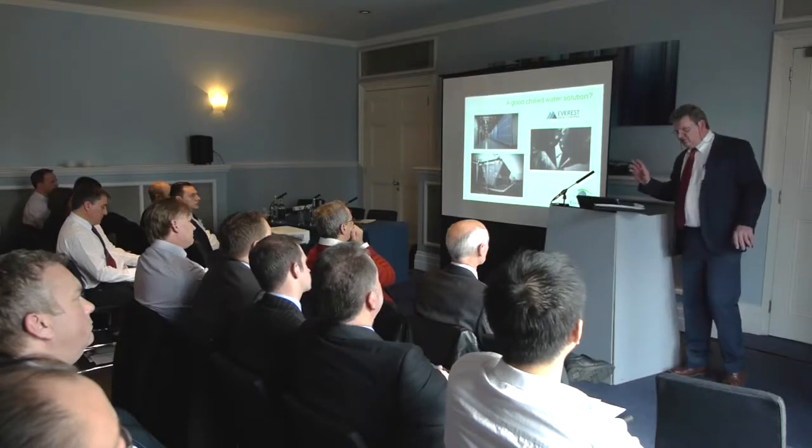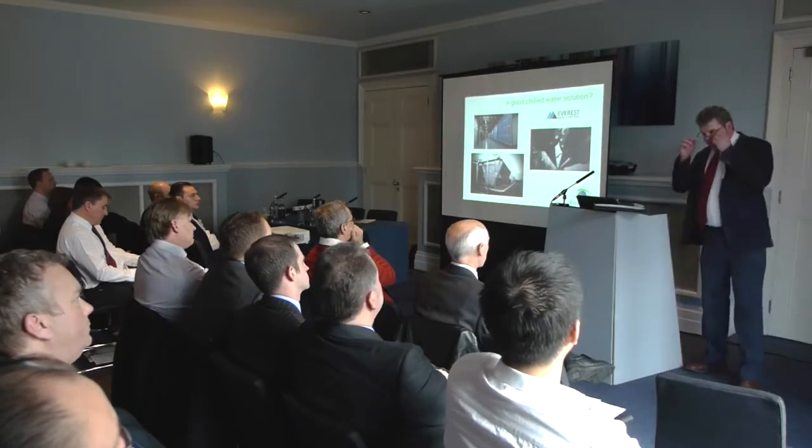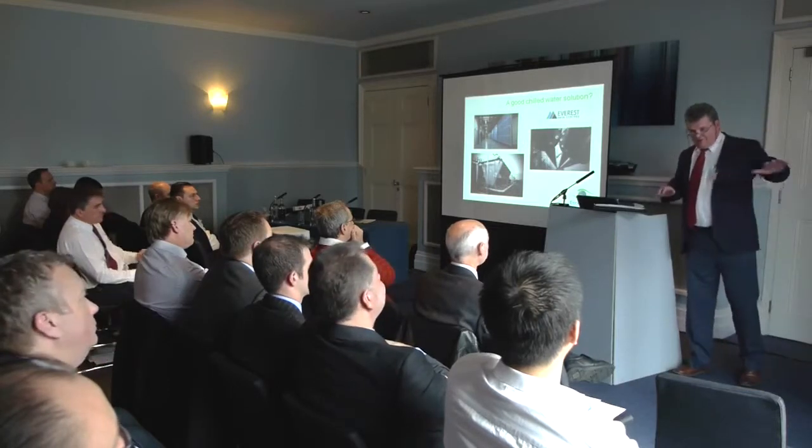One thing that most people don't understand or appreciate is the cube rule. We talk about Moore's law all the time, but people forget about the cube rule. If you're running fans or pumps, the energy follows a cube rule. So if you halve the speed of a fan, it only uses 12.5% of the energy. Slowing things down is great. Slowing fans down means there's less noise, less energy, less load on your filters, and so on. It's a good thing. Any control system should maximise the efficiency of your fans by minimising the speeds all the time.